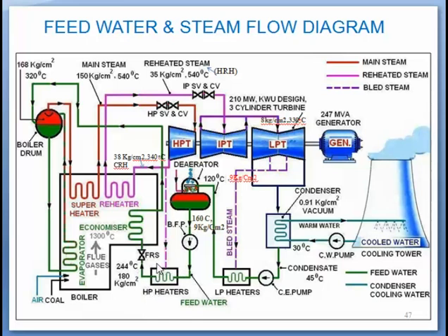The heating media for HP heaters are the bleed steam, one that comes from the IP and one that comes from the HP turbine. One thing one has to remember that in this LP heater and HP heater, the heating is only sensible heating. It means only there is a change in temperature, the phase will remain liquid only. And one more thing you can observe, at inlet the temperature of condensate to LP heater is at 45 degrees centigrade, then it is coming out at roughly 120 degrees centigrade.